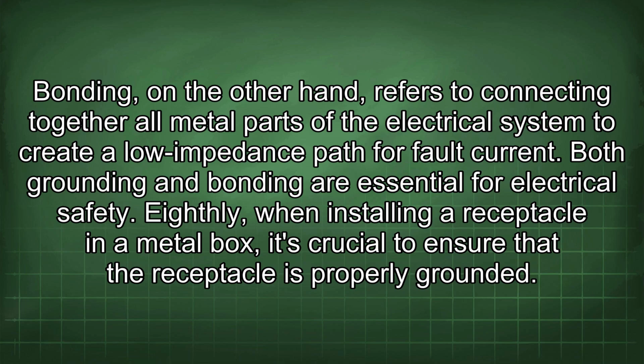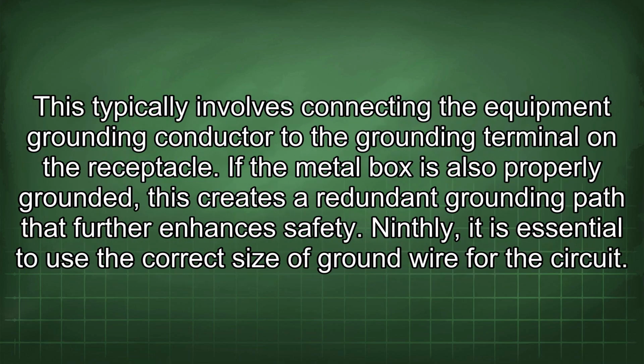Eighthly, when installing a receptacle in a metal box, it's crucial to ensure that the receptacle is properly grounded. This typically involves connecting the equipment grounding conductor to the grounding terminal in the receptacle. If the metal box is also properly grounded, this creates a redundant grounding path that further enhances safety.